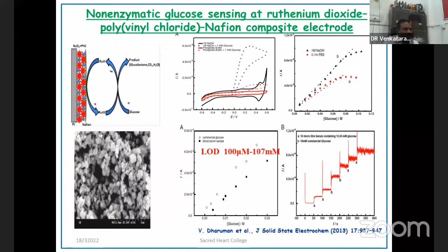For that, we can use different materials for developing the same type of glucose sensor. But our goal is to develop a sensor which gives highly reproducible results, not only in results but also in the fabrication process, for further sensor mass production. This sensor gives a linear range from 0.25 to 110 millimolar. You could ask that the PVC based sensor showed 100 micromolar, whereas when I use carbon nitride and platinum, this one is 0.25 millimolar. The linear range starts from 0.25 millimolar.